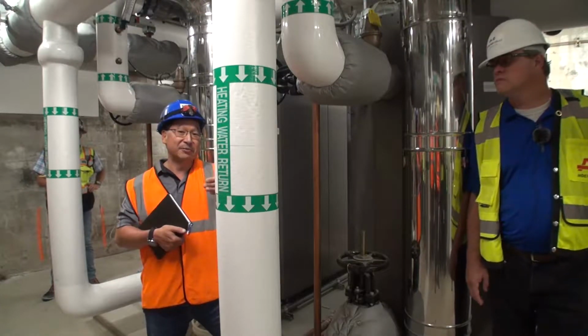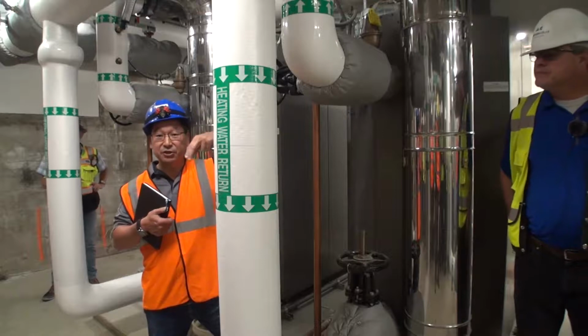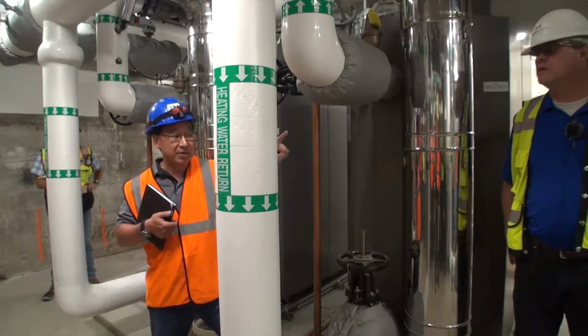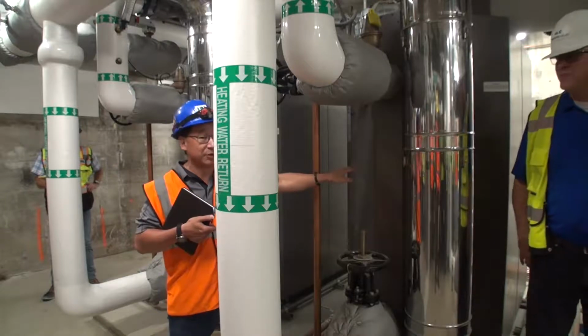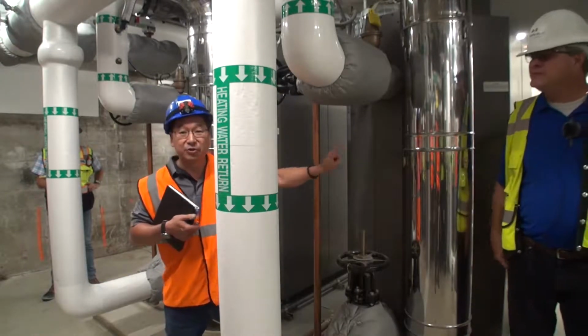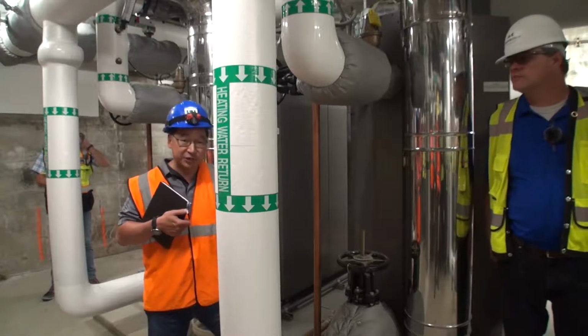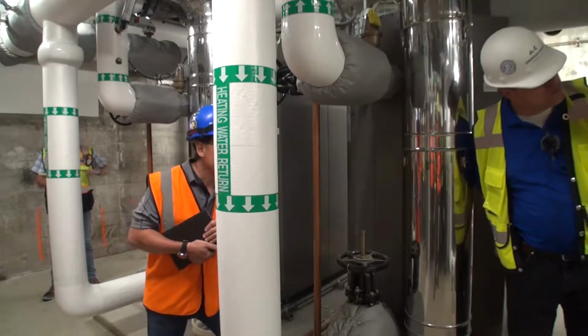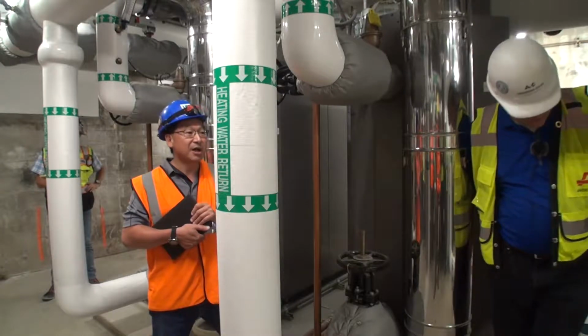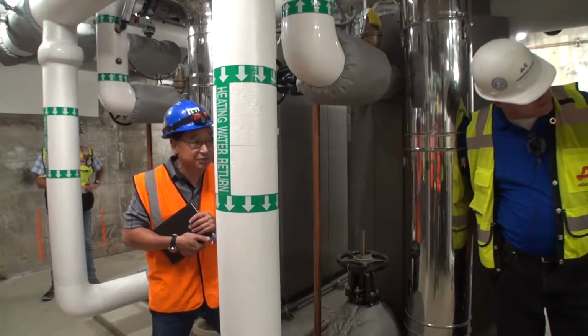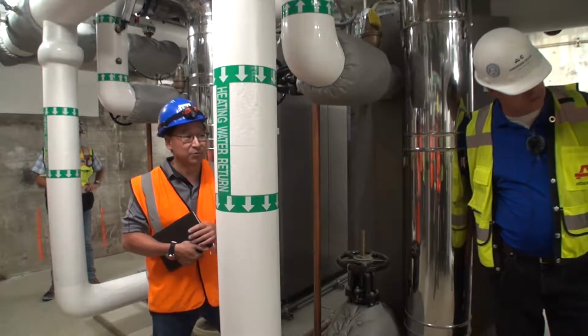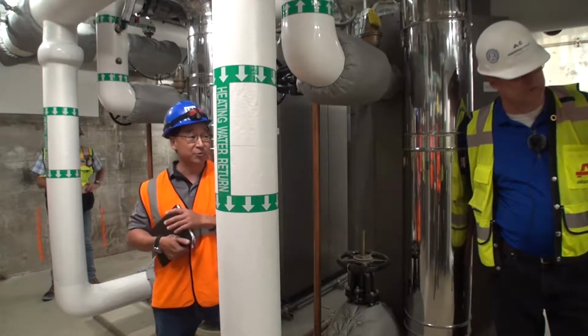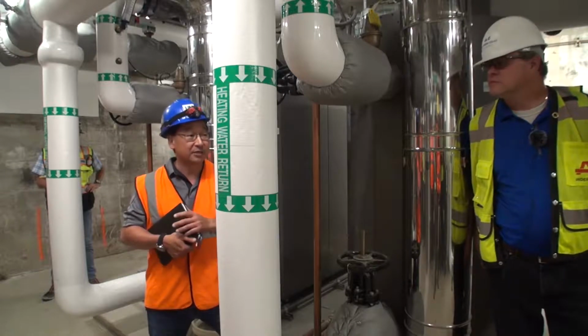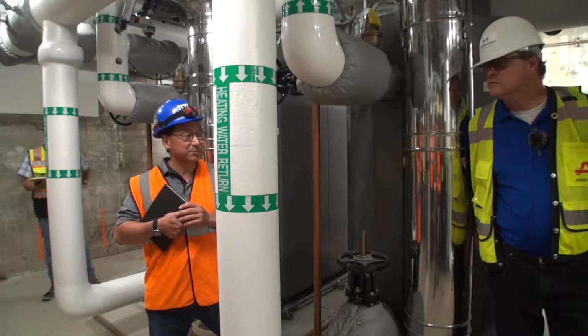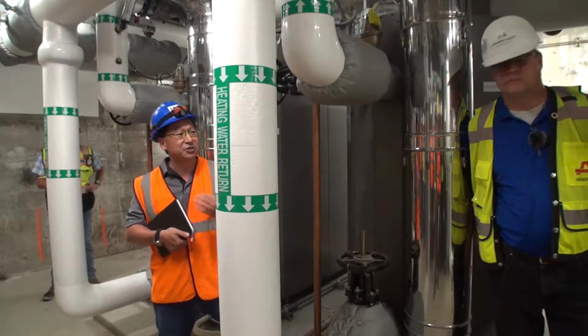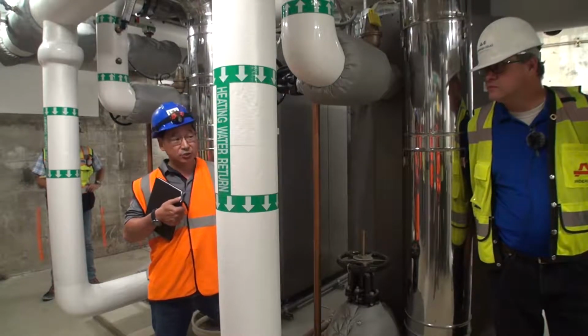And remember what I said about an alternate leader, we can program it and put in a different sensor that has 2 elements that will read. This boiler will read it, and this one. Only when it loses that one will this one take control. There are varying degrees of control that can be had. Is it set up that way? It is not. No. But that is an option that can be had. The sensor is about a $150 sensor, a little bit of labor, and we can push some buttons and help you folks do that. If the school district wants to entertain that, we can. We haven't been seeing it in the specifications because primarily Lochinvar is the only one that can do that that we know of.